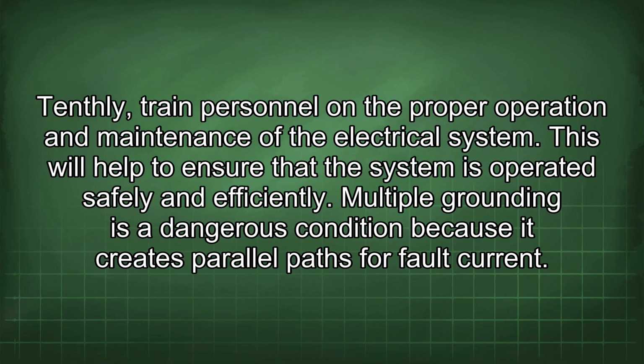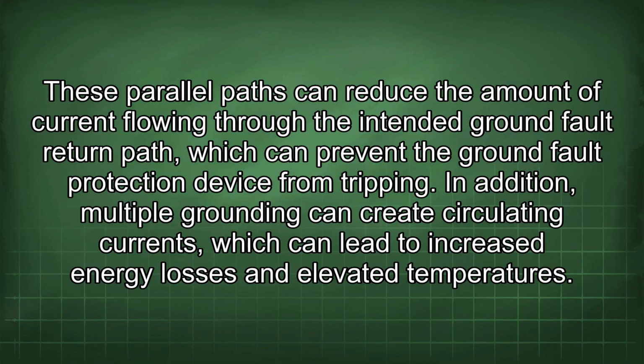Multiple grounding is a dangerous condition because it creates parallel paths for fault current. These parallel paths can reduce the amount of current flowing through the intended ground fault return path, which can prevent the ground fault protection device from tripping. In addition, multiple grounding can create circulating currents, which can lead to increased energy losses and elevated temperatures.